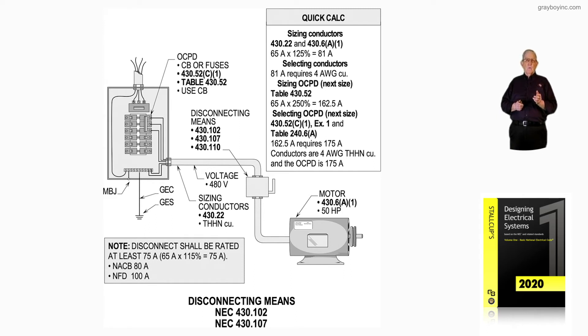The disconnecting means is 430.102, 430.107, 430.110. Here we're illustrating load, brake values, and current values. For horsepower, just look at 430.109A1. With this information, let's jump on the quick calc. In the quick calc, 430.6A1 to size your conductors will tell you you've got to use the table current for motors. If it's a three-phase motor, go to 430.250. If it's single-phase motor, go to 430.248.